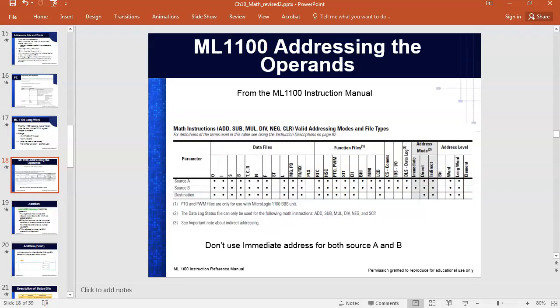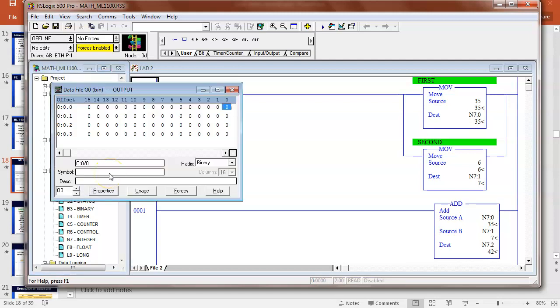So what happens when your PLC scans, it puts the information in these data files over here. Right now, if I was to get my information from output 0.0, I would get all zeros in there. But it's an addressable data file. When your PLC scans the inputs, it updates these data files, and then when it runs your program, it updates your output files. You understand?